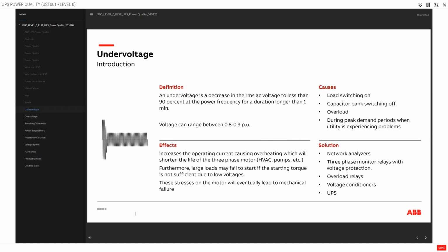Definition. An undervoltage is a decrease in the RMS AC voltage to less than 90% at the power frequency for a duration longer than 1 minute. Voltage can range between 0.8 to 0.9 per unit. Causes: load switching on, capacitor bank switching off. Overload. During peak demand periods when utility is experiencing problems. Effects.